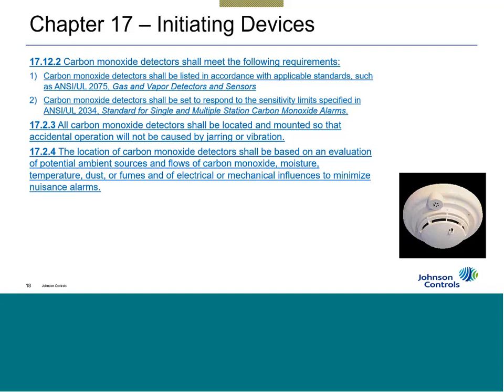And the other thing is our carbon monoxide devices, all manufacturers' carbon monoxide devices, need to have a date stamp on them. It needs to be encoded in the device, and the device needs to indicate an end-of-life signal. So for carbon monoxide, it's going to depend upon the manufacturer as to how many years you get out of their device. Some are 5 years, some are 7 years, some are 10 years. With Johnson Controls Autocall devices, you're getting 10 years out of your carbon monoxide devices. And it's from the date of when the device was manufactured.